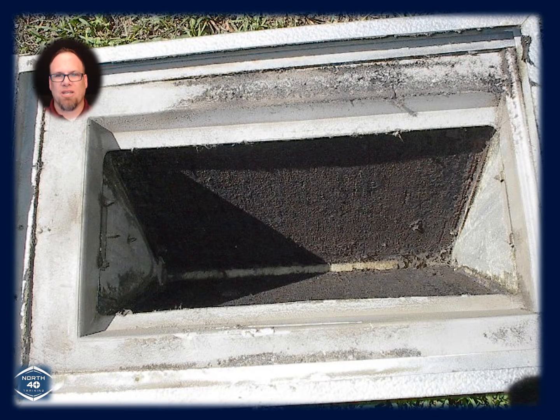Here's another fun picture. Now this is fun for us, but it wasn't fun at the time. This is just the opposite. Here we have the technical advisor going out on a job in which the furnace, a brand new furnace, kept tripping on limit. Nothing that they could do would get this thing to quit tripping on limit. Well, it was your standard installation in which the furnace was going to be replaced, but not the coil and not the air conditioning system at all.